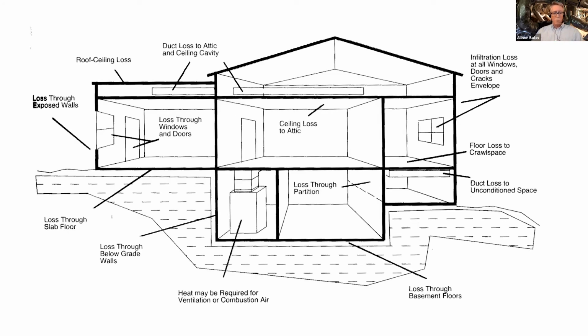Let's talk about the right way to do it now, and I'm talking about houses here, not big buildings, but the same basic procedures apply. This is a diagram straight from Manual J, which is the protocol for doing load calculations that the Air Conditioning Contractors of America has developed. As Mark already has told you, it's not the only way to do load calculations, but the basic principles inside each method are the same. You do the heat loss and heat gain through all the different surfaces, add infiltration, internal loads, all that stuff. So here's the diagram showing, for heating, the things that you have to account for.